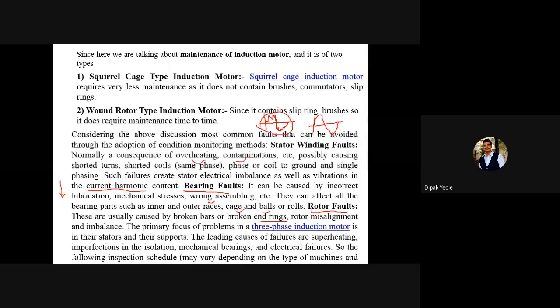Rotor misalignment and imbalance. The primary focus of problems in a three-phase induction motor is in their stators and their supports. The leading causes of failures are overheating, imperfections in the insulation, mechanical bearings, and electrical failures. So the following inspection schedule, which may vary depending on the type of machine and the importance of that machine, must be carried out for the induction motor.